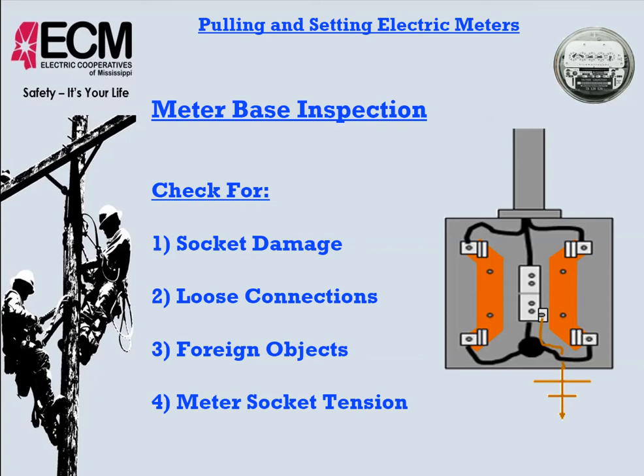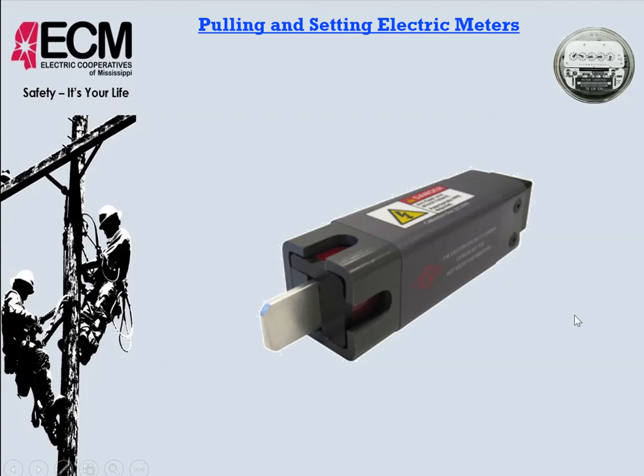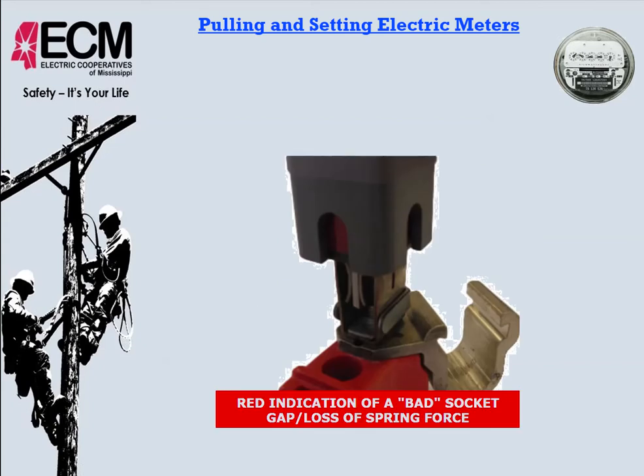And if it is a loose connection, it's definitely going to burn up the meter base and sometimes our meter as well, and it's also a trouble call. They make a neat little device called a meter socket lug tension tester, and you see that it has a flat tab here that is similar to what's on the back side of a meter.